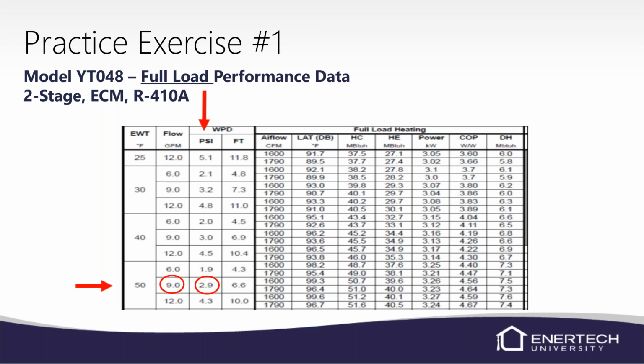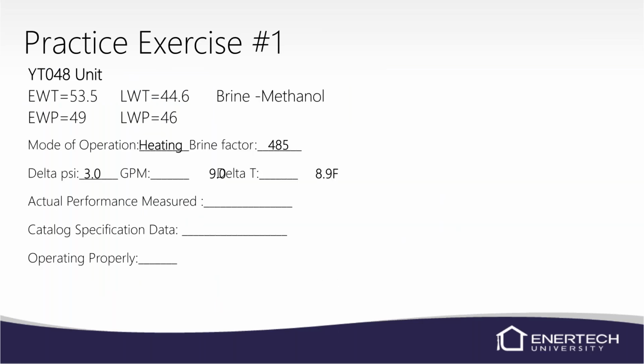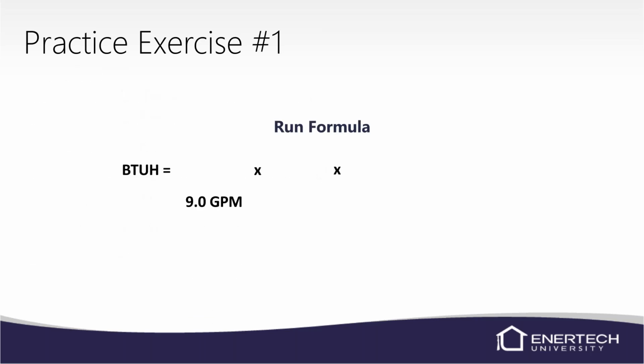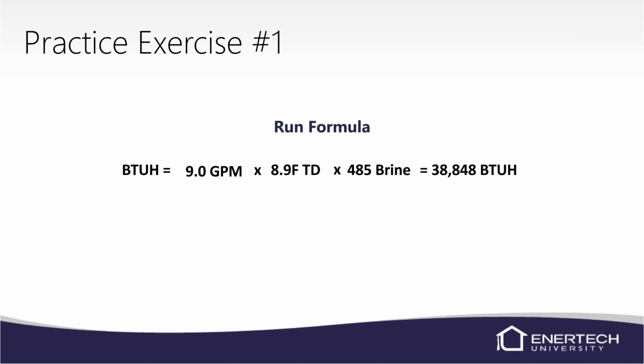Again, back to this example. So we know we have 9 GPM. Now we know our GPM, we know our temperature difference. Sorry about that, I need to adjust that slide a little bit. So now we've got all the numbers that we need to measure the performance. We can just do the math, run the formula: GPM of 9 times our temperature difference of 8.9 times our brine factor, or fluid factor, of 485. So 9 times 8.9 times 485 is going to give us a number of 38,848 BTUs.